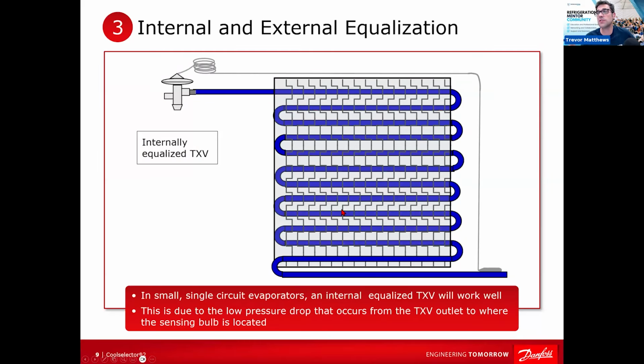Let's talk a little bit about internal and external. All right. Okay, so go back to what we're talking about, the forces on a TXV. The evaporator pressure that's underneath that diaphragm and your spring pressure, that's what the sensing bulb needs to overcome. And again, if it's set for 7 degrees of superheat, 3.5 Kelvin or 4 Kelvin or whatever it is, or range, that is what's set.